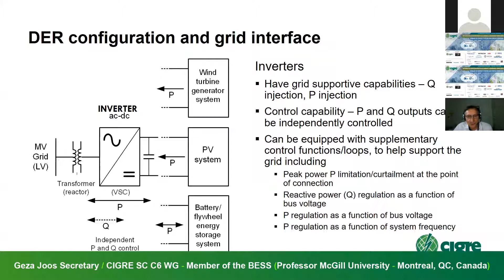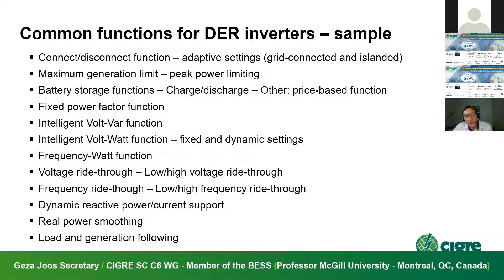These are the common functions. They're defined in a number of IEC documents, and also in an EPRI document—EPRI started the term 'common function' or 'intelligent function,' which comes from an EPRI document. It includes a whole slew of functions like volt-var, volt-watt, frequency-watt, and ride-through voltage and frequency functions. Again, the issue here is that you cannot accumulate functions—you have to decide a priority order and which ones you will implement.